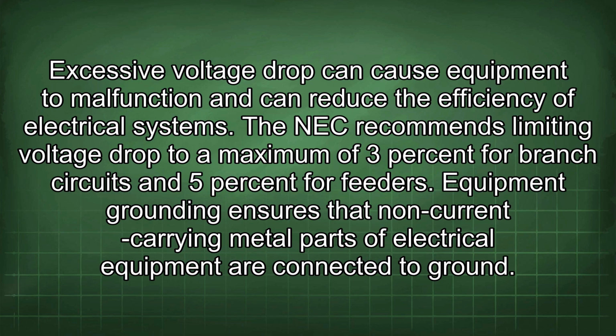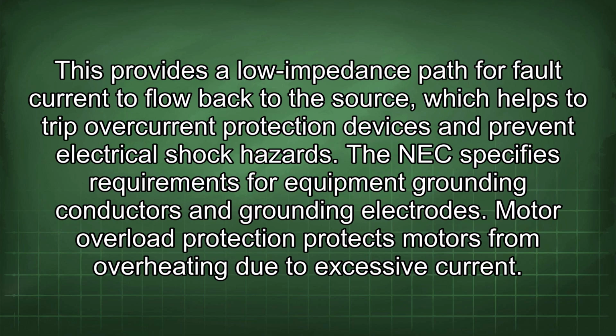Equipment grounding ensures that non-current carrying metal parts of electrical equipment are connected to ground. This provides a lower impedance path for fault current to flow back to the source, which helps to trip overcurrent protection devices and prevent electrical shock hazards. The NEC specifies requirements for equipment grounding conductors and grounding electrodes.